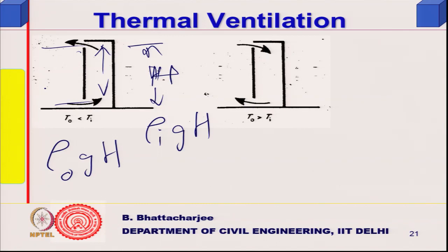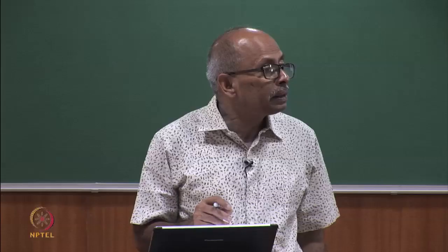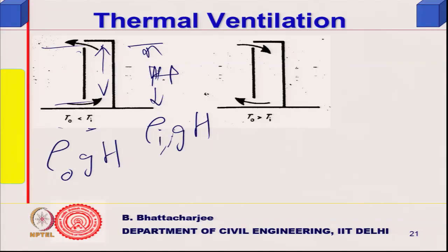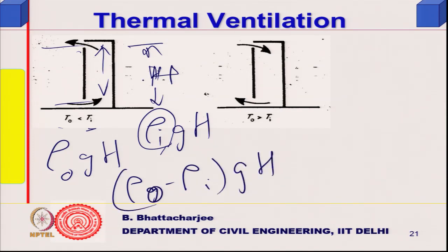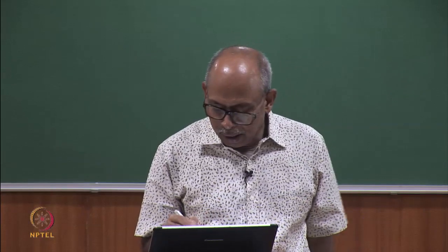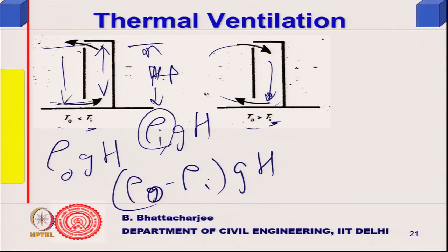If inside temperature is greater than outside, inside density is lower, so inside pressure is lower. The driving pressure is (rho-outside minus rho-inside) times g times H, pushing air inward at the bottom. If outside temperature is greater, density is higher inside and pressure inside is more, causing flow in the opposite direction — this is the stack effect.